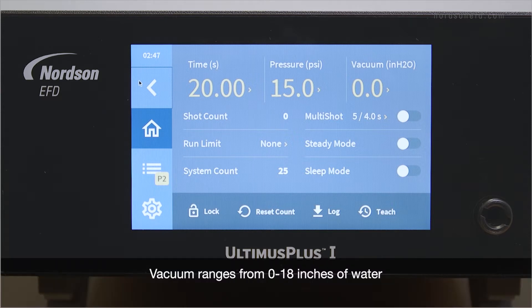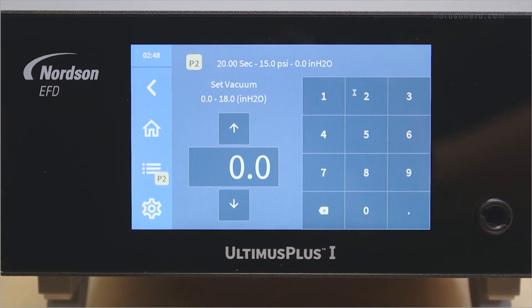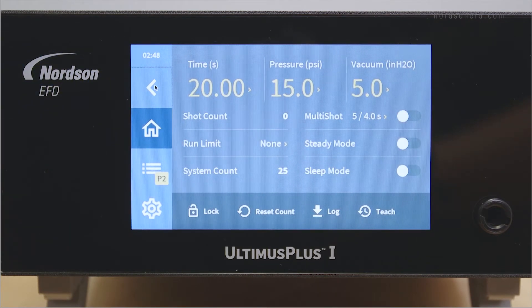Vacuum ranges from 0 to 18 inches of water. To change the vacuum, touch the vacuum section on the touch screen. Enter a vacuum value and wait a second for the UltimusPlus to accept it. Then hit the back arrow to return to the home screen. We recommend you start the vacuum at 0 inches of water and slowly increase until you reach the desired setting.